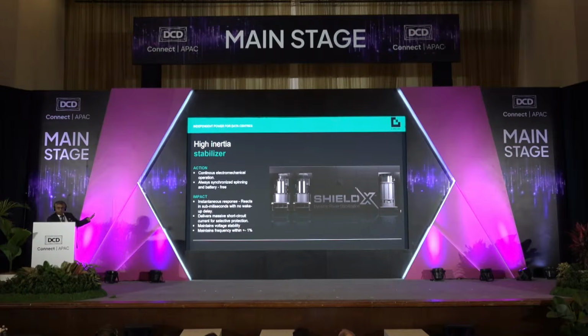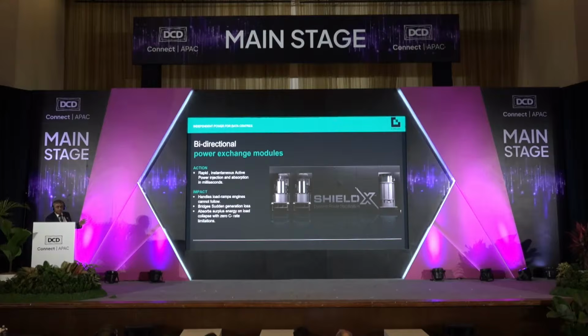Now, having looked at one of the components, which is the stabilizer, let's look at the second component, which is the power exchange module. These power exchange modules are rapid, instantaneous, and provide active power and absorb active power as required. They handle load ramps which engines cannot follow, bridge sudden generation loss, and absorb surplus energy.